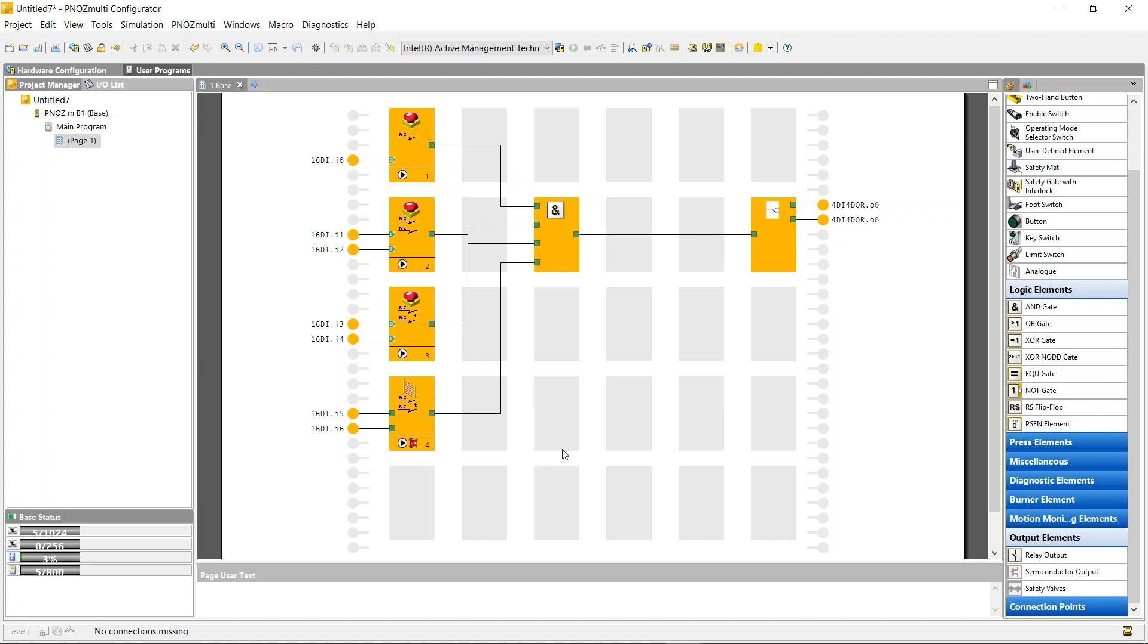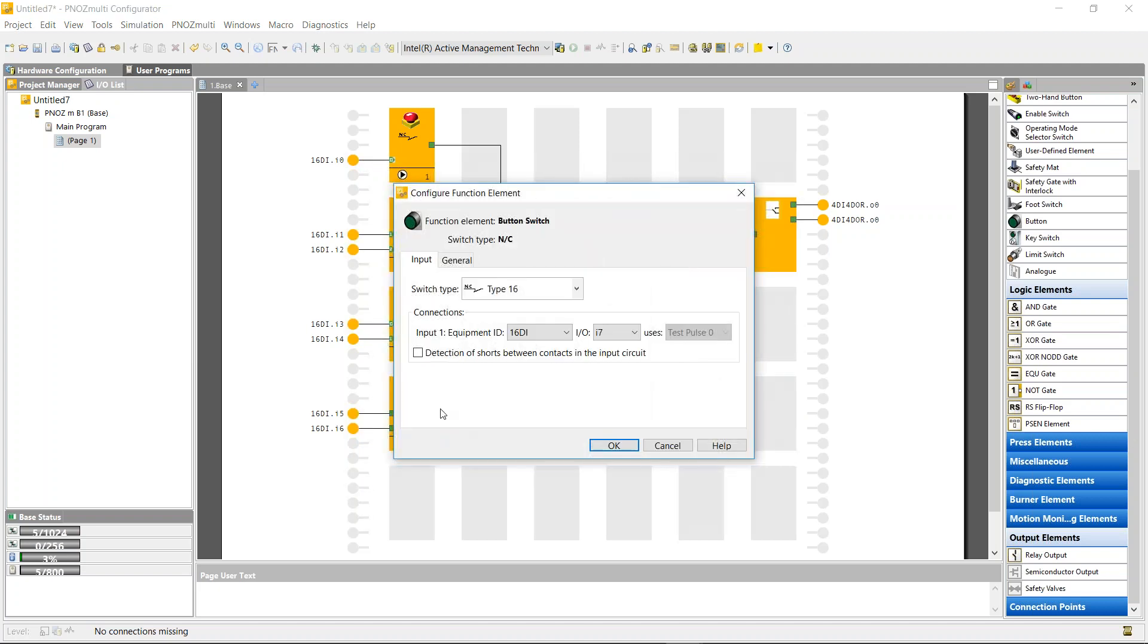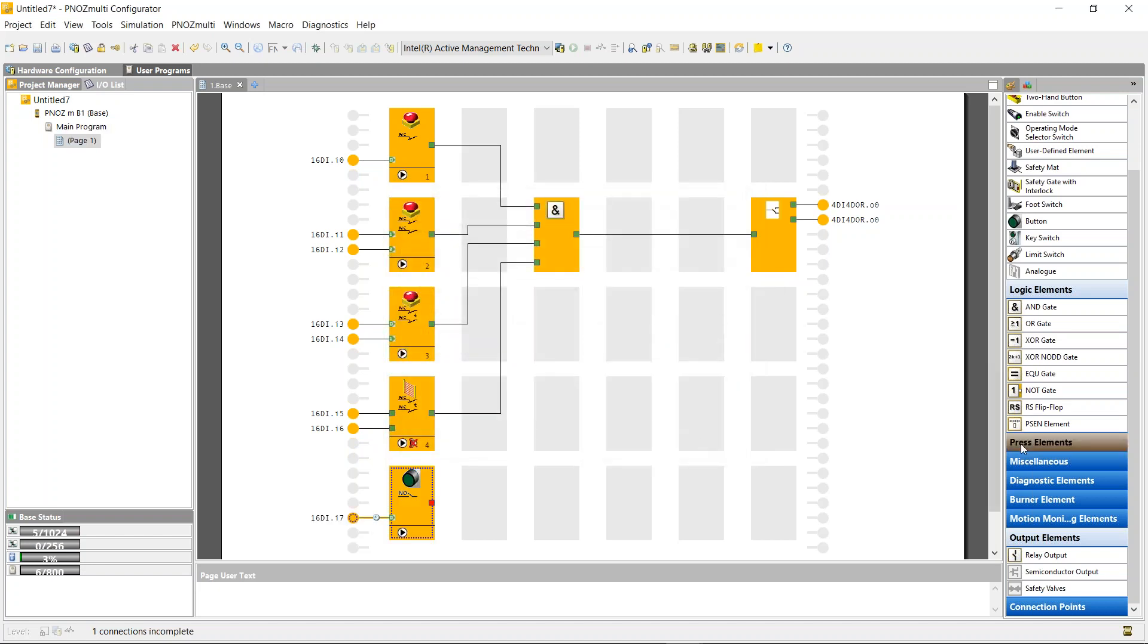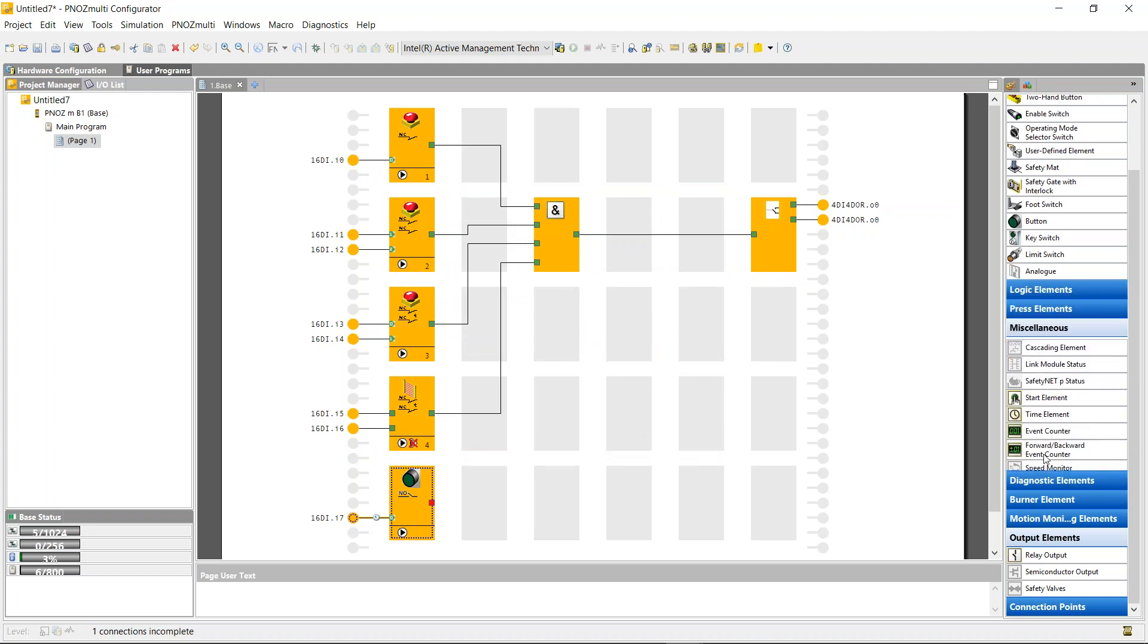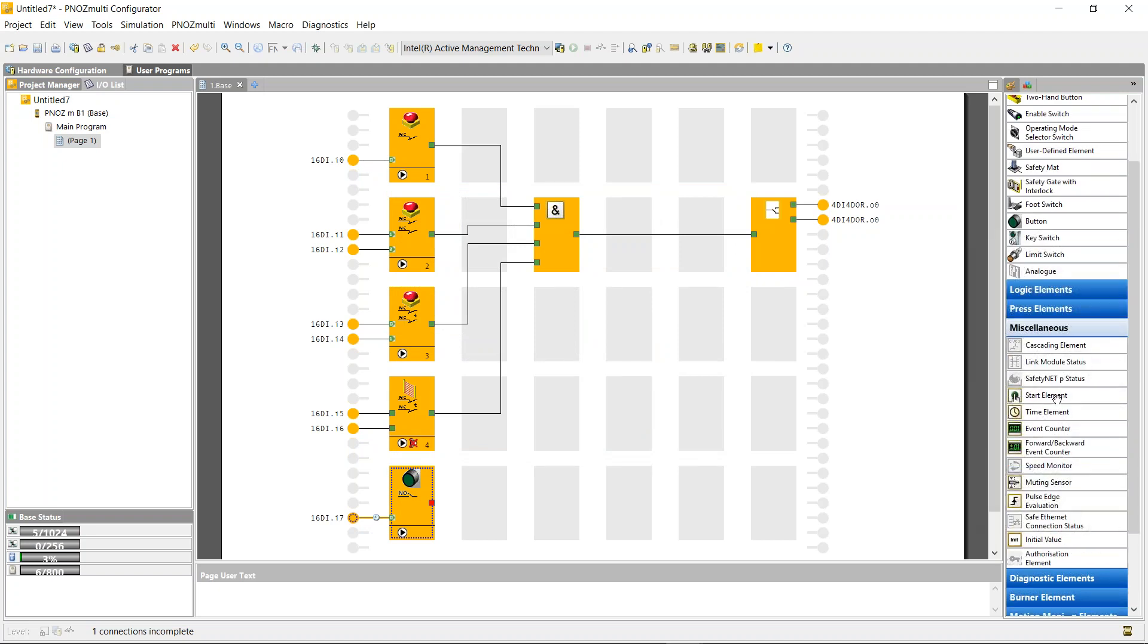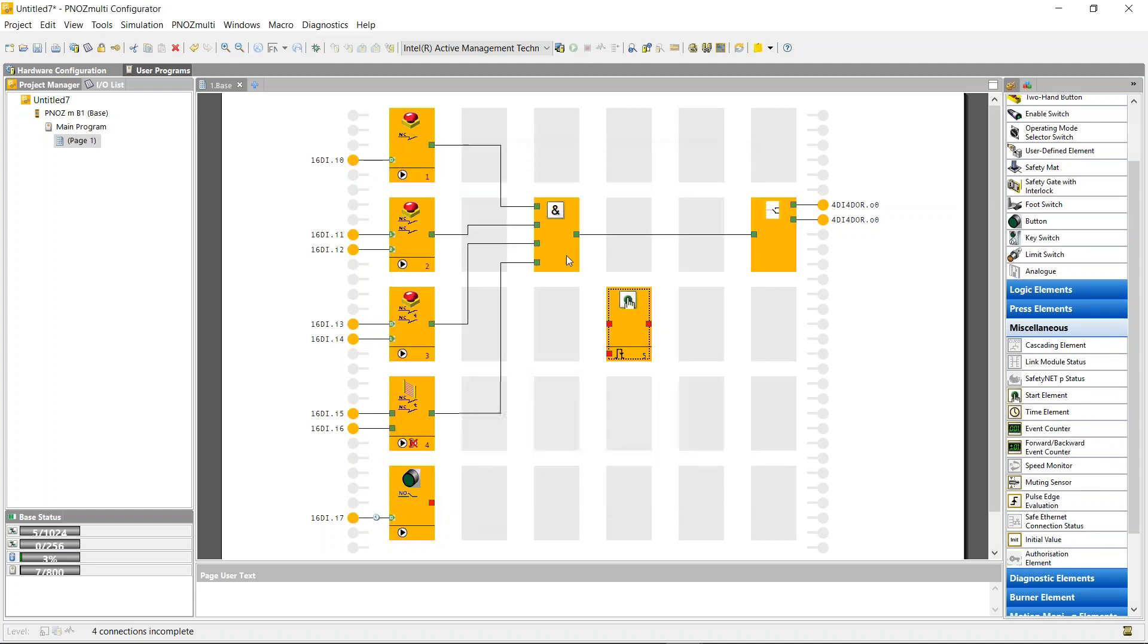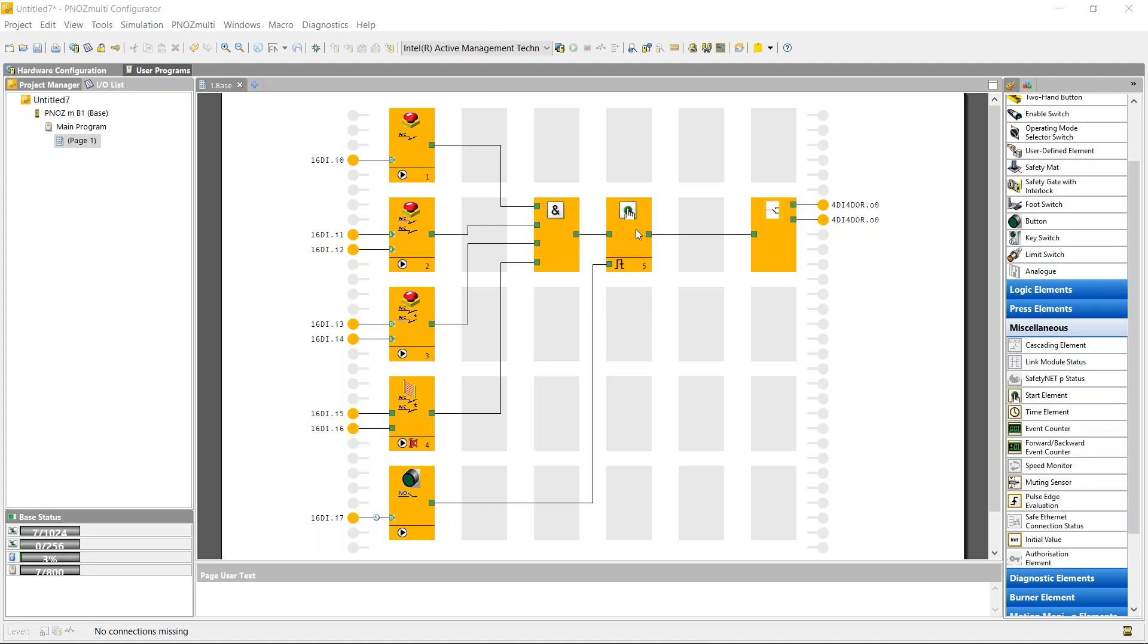If I wanted to put in a manual reset into the circuit, I could just use a normally closed push button that I have on the control panel. I could change this to normally open at the 16 digital input I7 and use detection of shorts. In the miscellaneous, you'll see a start element. If I use that to activate my manual reset, I can just delete this line and I've now just added in the reset button.